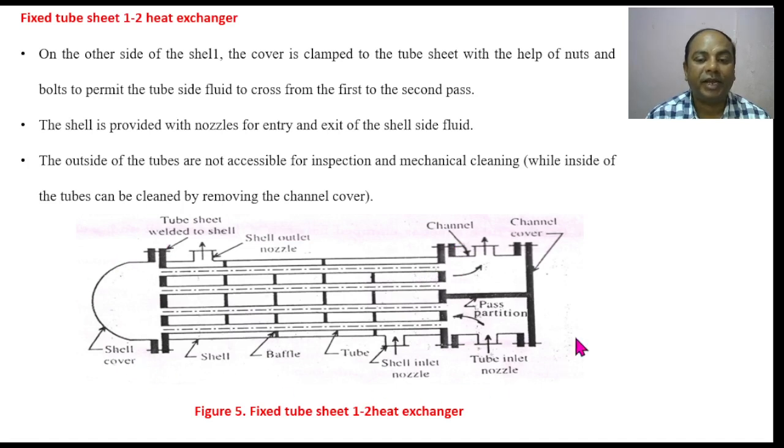In this arrangement there is a possibility, however, that mechanical cleaning is the drawback of this fixed tube heat exchanger. Inside cleaning of these tubes is required, as scale formation may take place inside the tube, as one of the fluids continuously runs through the tubes.